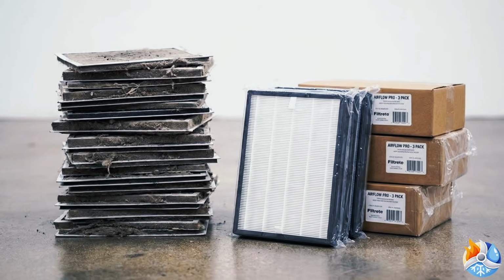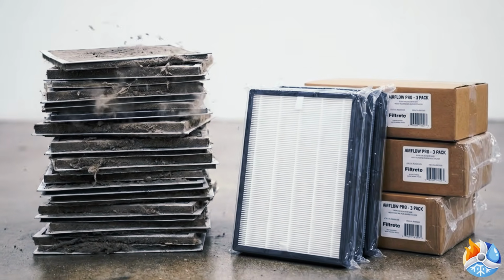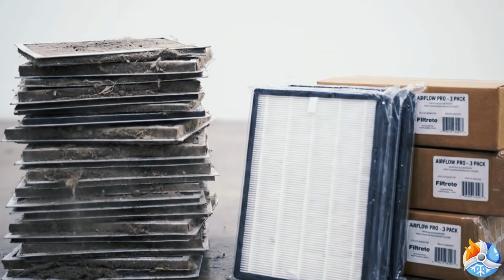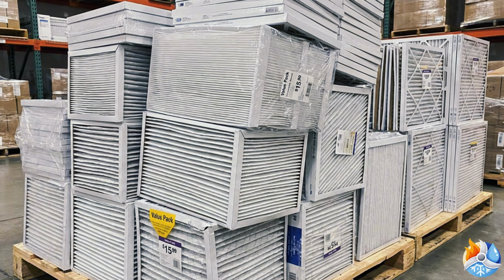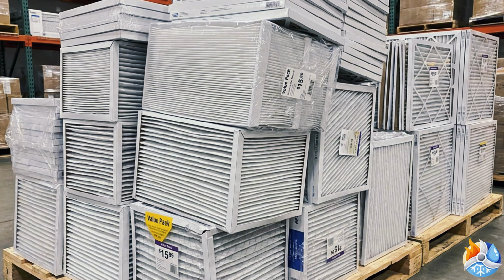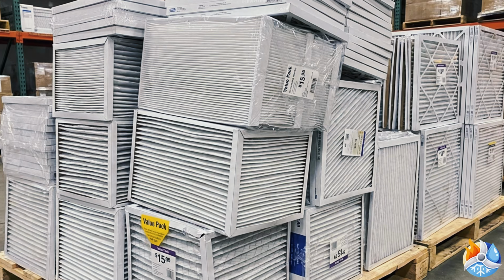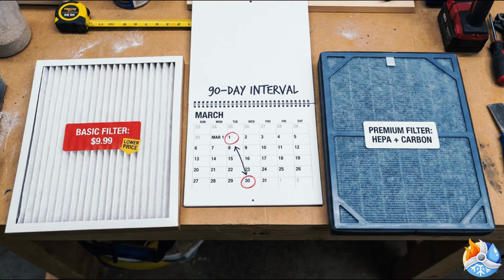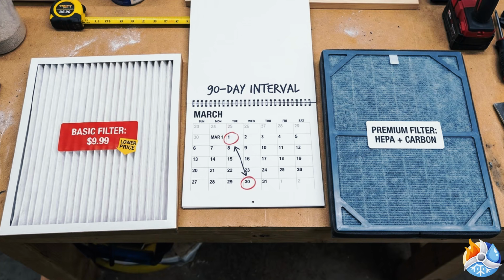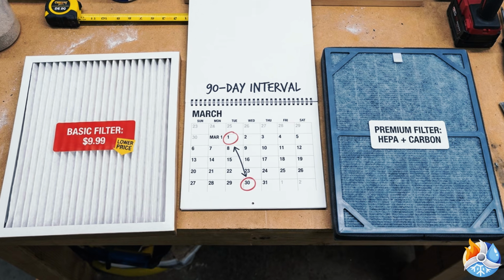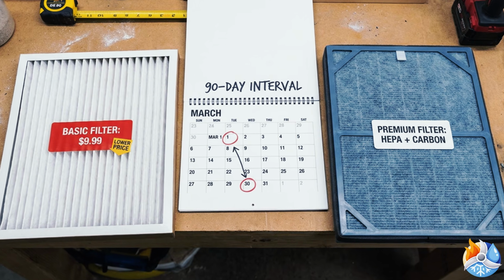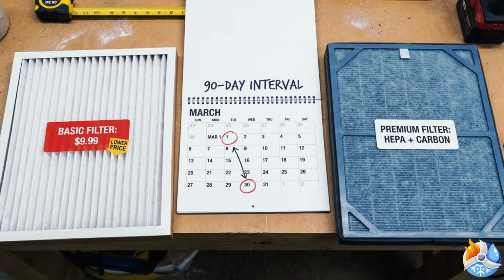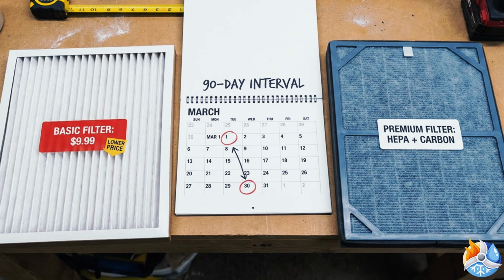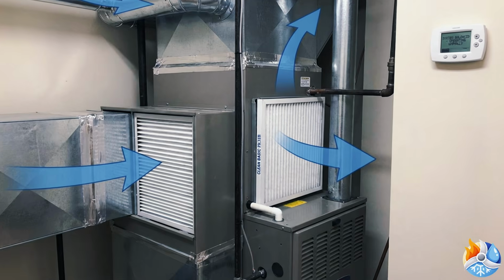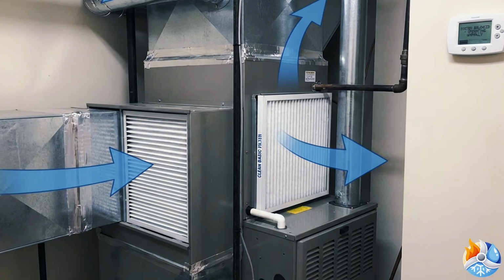So that quarterly filter, you might be replacing it 8 to 10 times a year. At $30 each, that is $240 to $300 annually, just in filters. Compare that to a quality, basic pleated filter at $5 to $8, changed every 90 days. That is $20 to $32 a year. And the cheap filter is not stressing your equipment.